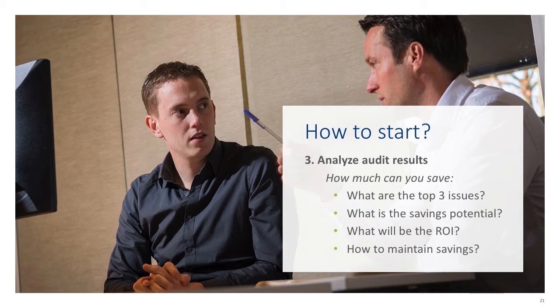And if you know what parts to order, like a new gasket or, worst case, another compressor, you can calculate the return on investment, based on your kW consumption and an estimation of the amount of energy you're going to save. So it's a way to really have a well-founded approach for the next steps. And also, you can discuss how to maintain those savings afterwards. Do we need additional monitoring? For example, we had a case where during an audit, issues were revealed with a bag filter house. In the end, the decision was to put in a permanent flow meter, because this will happen again, along with a monitoring flow sensor and some other equipment for that particular piece of equipment.